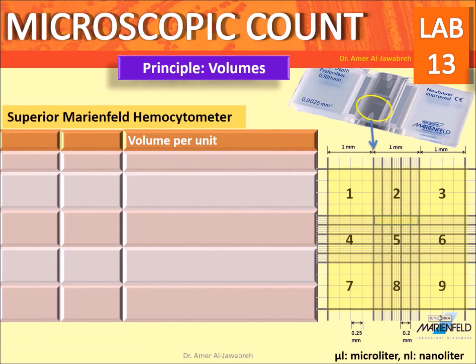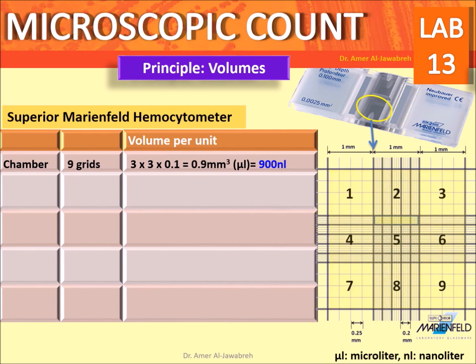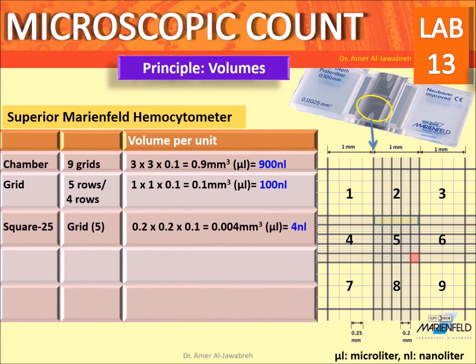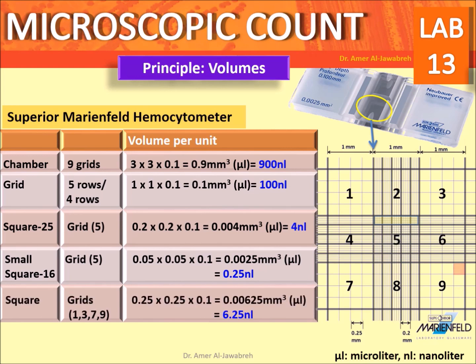Principle volumes for the Superior Marienfeld hemocytometer: each chamber consists of 9 grids with a total volume of 900 nanoliters. Each of the 9 grids has a volume of 100 nanoliters. Each of the 25 squares in grid 5 has a volume of 4 nanoliters. Each of the 16 smaller squares in grid 5 has a volume of 0.25 nanoliters.